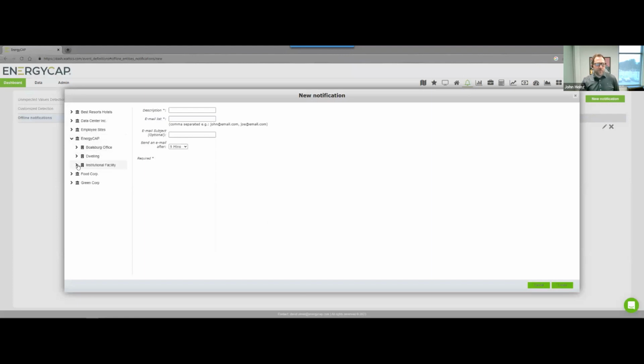This allows you to pick any point - let's say my chilled water point I'm monitoring at a building - and set up an alert to email me after a certain time period if I'm not receiving readings. This is really helpful to alert your team if a meter goes offline, there's a connectivity issue, or even if file exchanges for importing reads aren't triggering. I can say, if I haven't received a read in 12 hours, notify me that a meter's offline. It's helpful to diagnose issues before you run into a period where days go by without reads. So that's the offline alarm type.